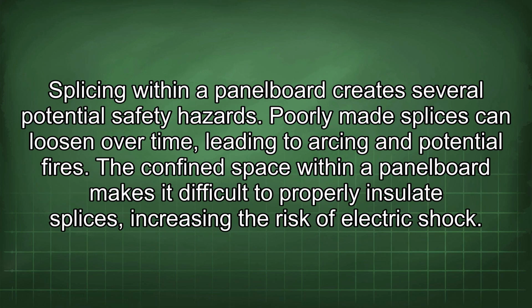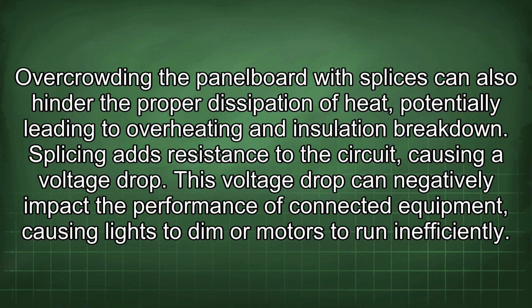Splicing within a panel board creates several potential safety hazards. Poorly made splices can loosen over time, leading to arcing and potential fires. The confined space within a panel board makes it difficult to properly insulate splices, increasing the risk of electric shock. Overcrowding the panel board with splices can also hinder the proper dissipation of heat, potentially leading to overheating and insulation breakdown.